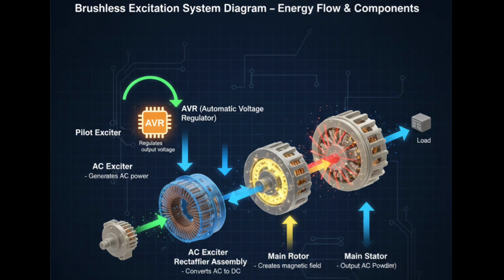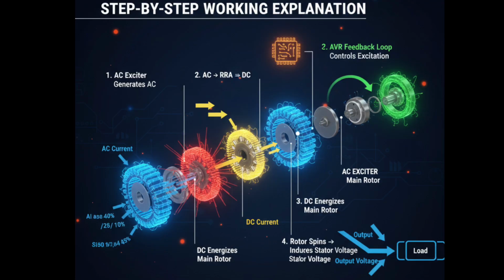During troubleshooting, visualizing this diagram helps locate faults such as rectifier diode failure, exciter winding issues, or AVR malfunction. Step-by-step working explanation. Now let's break down the working of the brushless excitation system step by step, with reference to the 3D graphics on your slide. Notice the flow of AC current from the exciter, shown by the blue arrows, which passes to the rotating rectifier assembly highlighted in yellow.